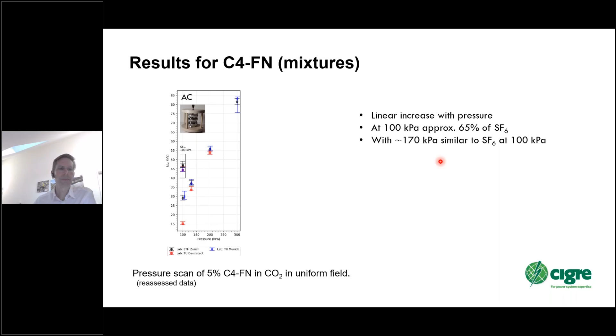Then we went on to perform the weakly non-uniform and the strongly non-uniform tests under AC and LI conditions. Here it is interesting to note, and you see the comparison of the gas with SF6. First of all, you can see like groups here, which means there are tests from more than one laboratory. Usually we tried to have at least two, ideally more, of the same tests performed in different laboratories to see how intercomparable and trustworthy the tests and test procedures that we described are.